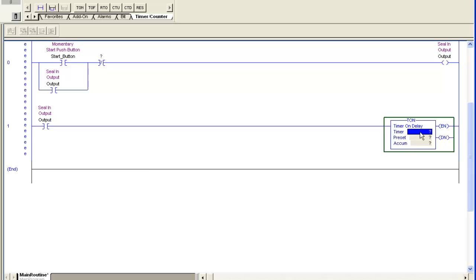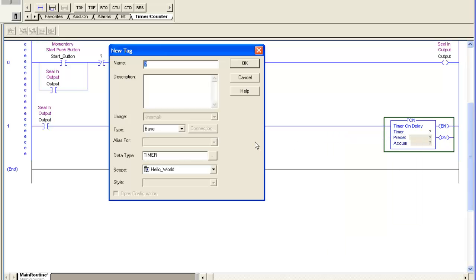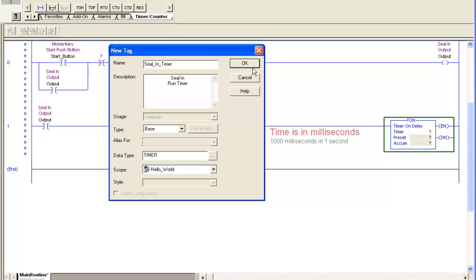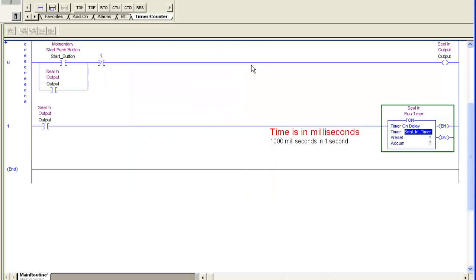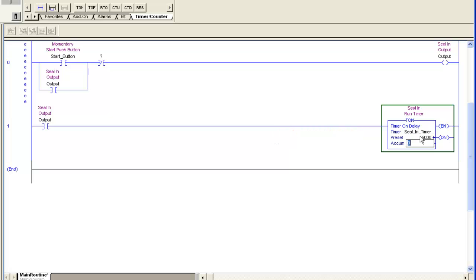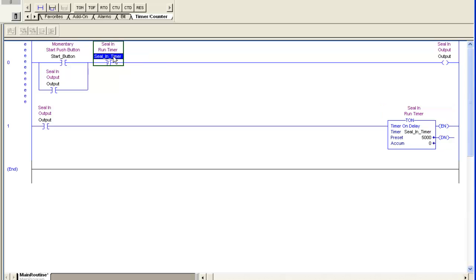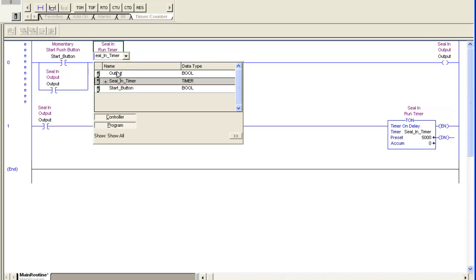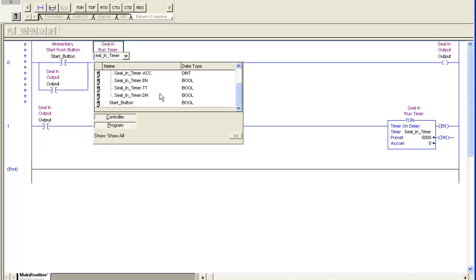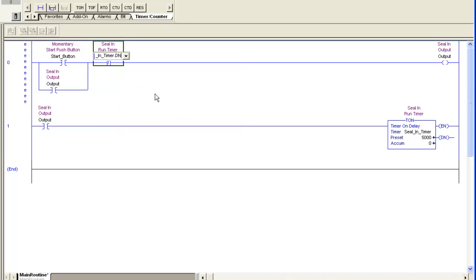And I'm going to create a timer, new tag. Give it a name, give it a description. The thing about RSLogix 5000 is all time is in milliseconds. I want this to be a five-second timer, so I'm going to go ahead and put in 5,000 milliseconds. Then I'm going to drag the timer bit and come to the element of timer done. Put that in there.